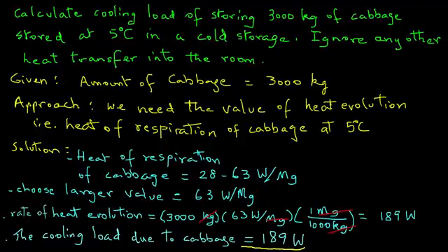So this example shows that if we were to consider only the product heat that is given off, that we must remove with our refrigeration system, then we must design our system with a cooling load of 189 watts.